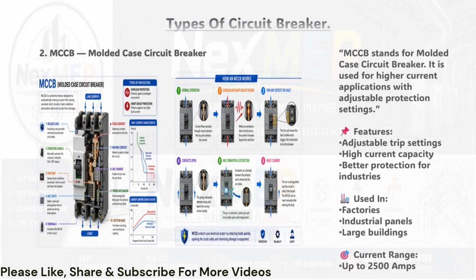Next up is the MCCB, molded case circuit breaker. Think of this as the heavy-duty version of the MCB. While an MCB handles up to 100 amps, an MCCB can handle up to 2,500 amps, making it ideal for industrial and commercial applications. You'll find MCCBs in factories, industrial panels, and large buildings. What makes MCCBs special is that they have adjustable trip settings, meaning you can tune the protection thresholds based on the specific load requirement.